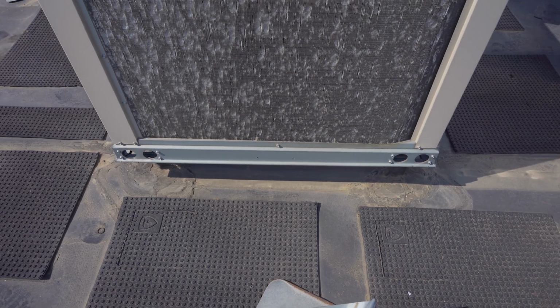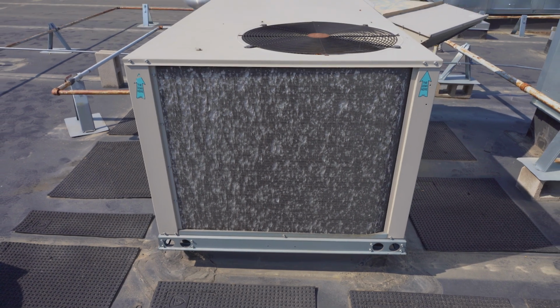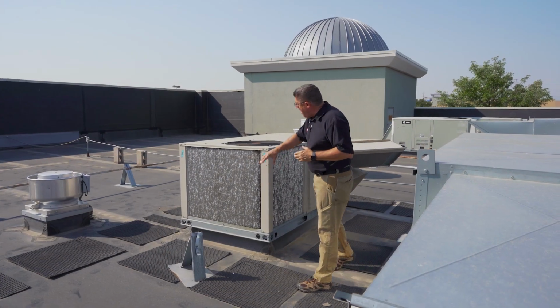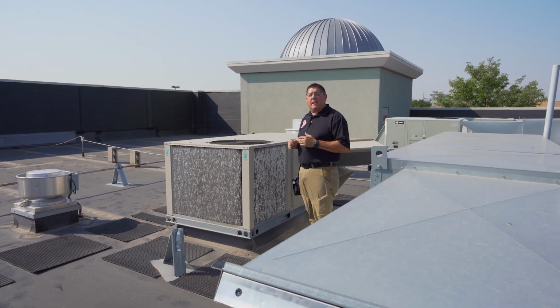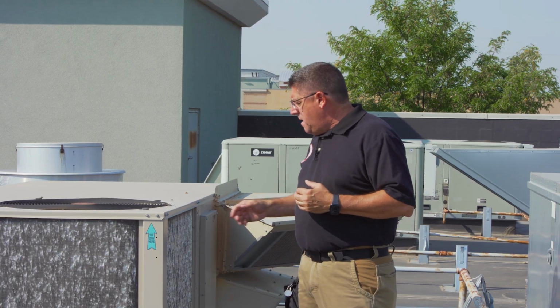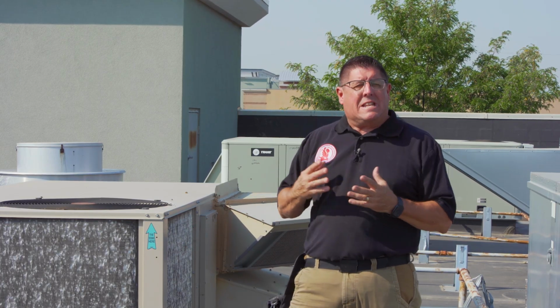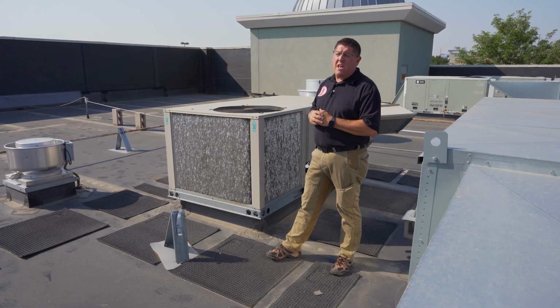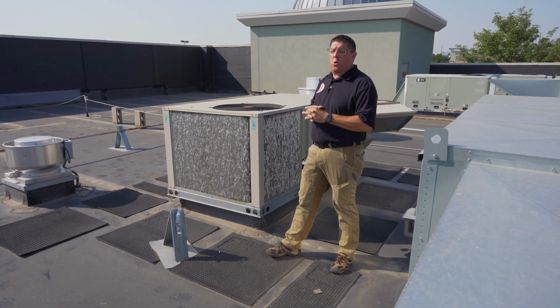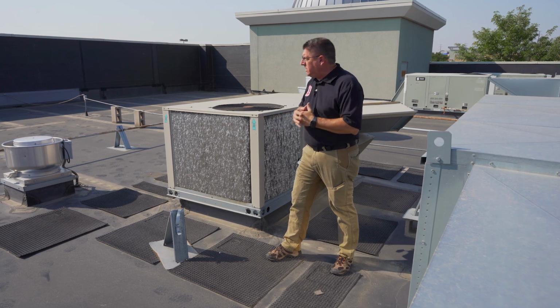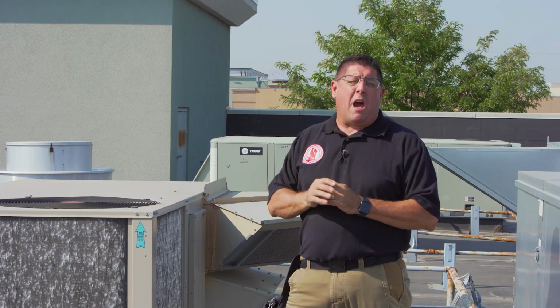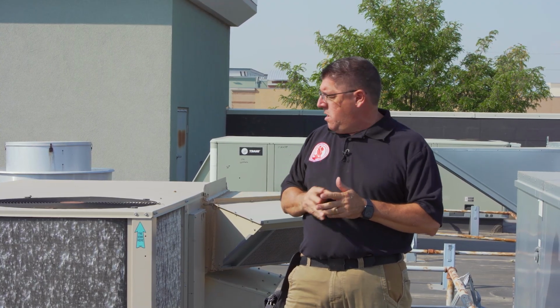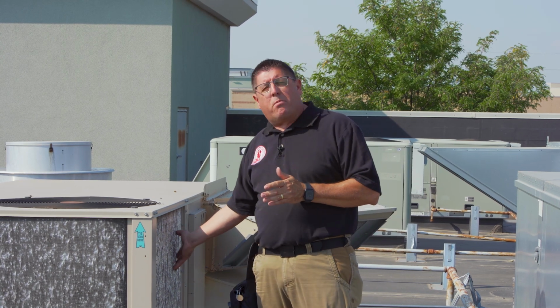Then we migrate around the rest of the outside of this packaged unit, and we'll find the fins. If you look at these fins, I think it's pretty obvious that we have a tremendous amount of hail damage present. That's what all these little holes are, or we have people up here just kicking it a lot. I think it's hail damage. The rule of thumb has always been we can dent up to 20% of the fins and not ruin the cooling potential. In this particular case, as we're inspecting the cooling side, I might think that the fins are part of the issue, but we'll have to look for that as we operate this.